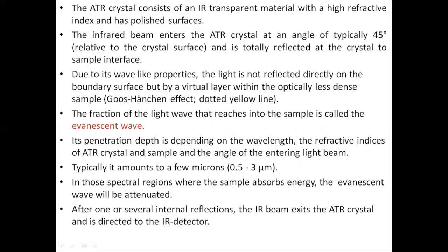The ATR crystal consists of an IR transparent material with a high refractive index and has polished surfaces. The infrared beam enters the ATR crystal at an angle of typically 45 degrees relative to the crystal surface and is totally reflected at the crystal to sample interface. Due to its wave-like properties, the light is not reflected directly on the boundary surface but by a virtual layer within the optically less dense sample. The fraction of the light wave that reaches into the sample is called the evanescent wave.